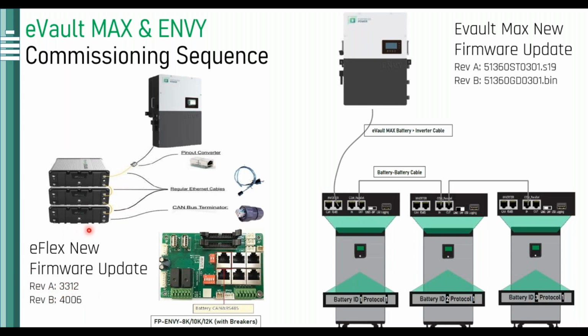If it starts with 3, you will give it the firmware update that starts with 3. If the version is 4, then you would give it the firmware version that starts with 4. Very simple, very straightforward. Okay, and same with the eVault Max. The only difference here would be that one has the STO version that is Rev A, and one has the GD version that's Rev B. So what I'm trying to say is when updating the firmwares, we would update it with the respective version according to what shows up on the software, right?